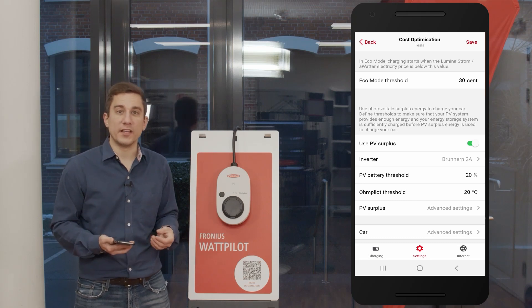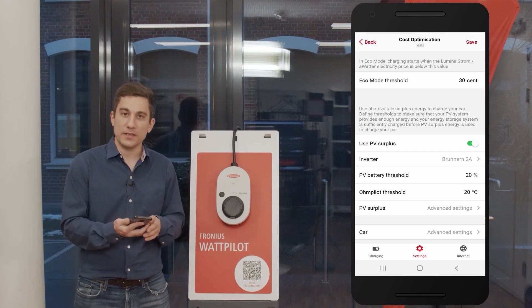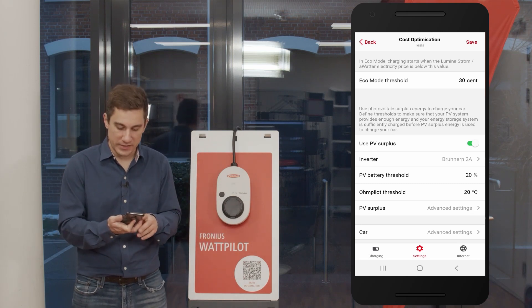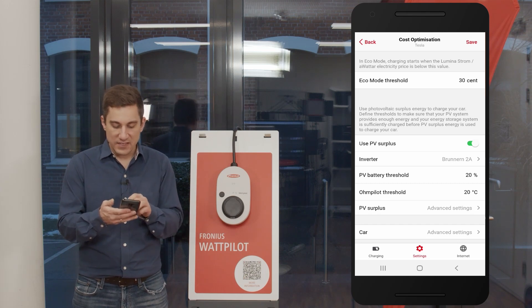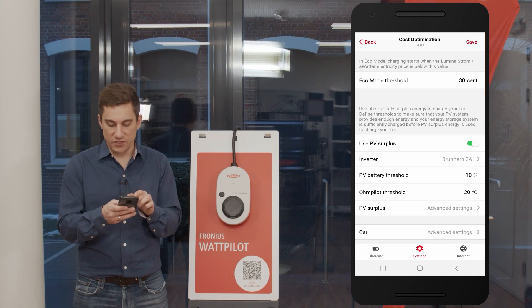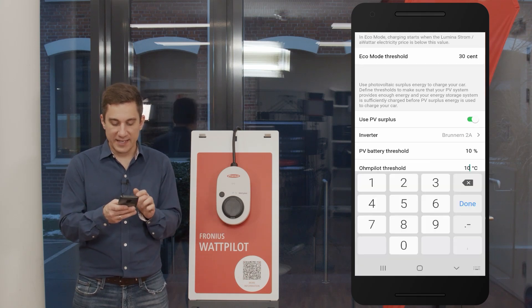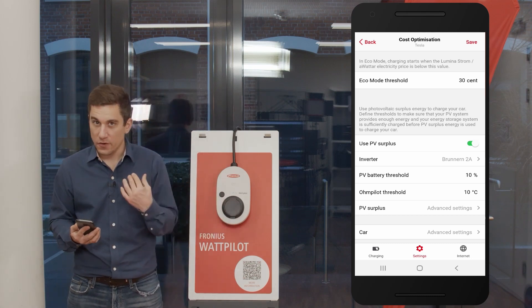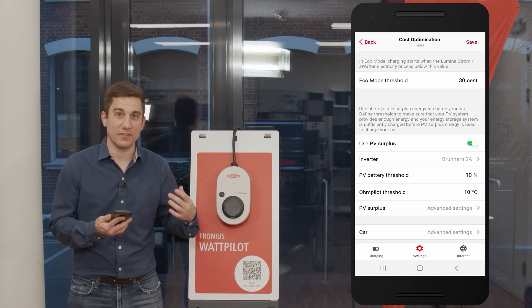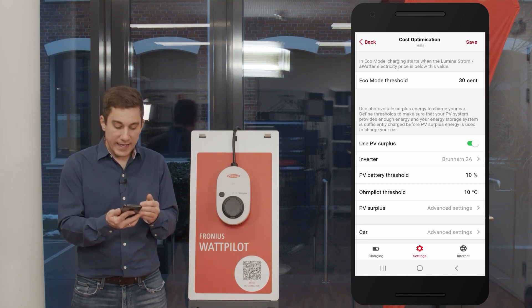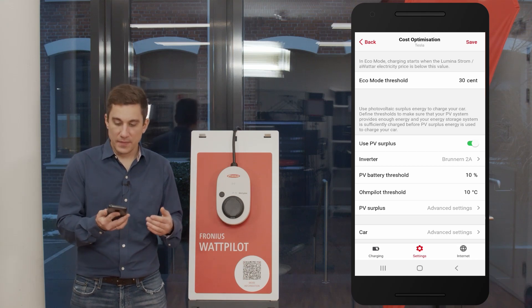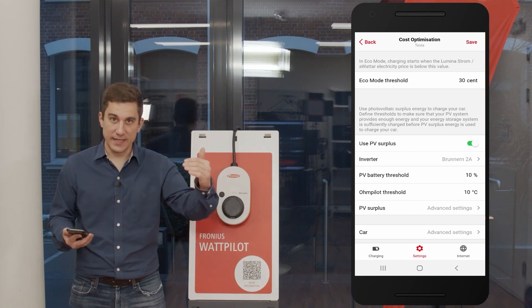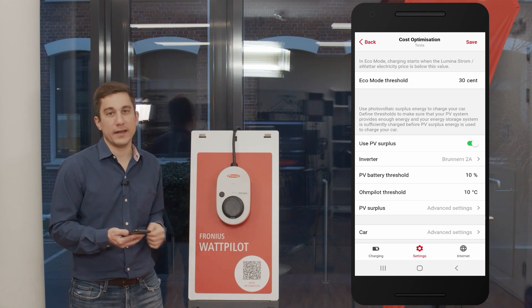For example, if you want to make sure the Wattpilot uses PV surplus energy first and has a relatively high prioritization, you can set the PV battery threshold to 10% state of charge and the Ohmpilot threshold to only 10 degrees Celsius. In this first example, the Fronius inverter will ensure the PV battery is charged to at least 10%, and after that threshold is met, the Wattpilot will receive the energy.